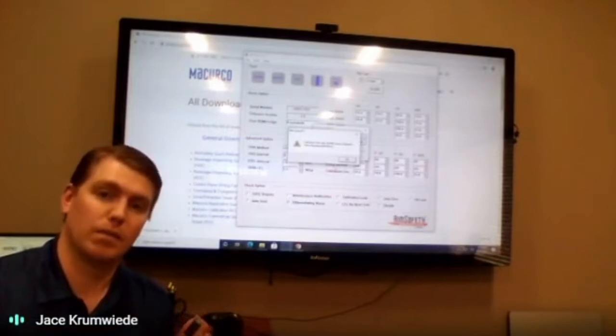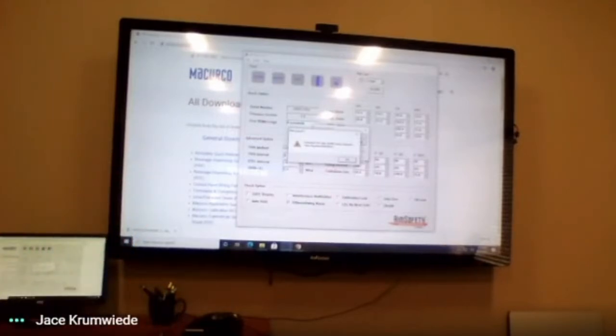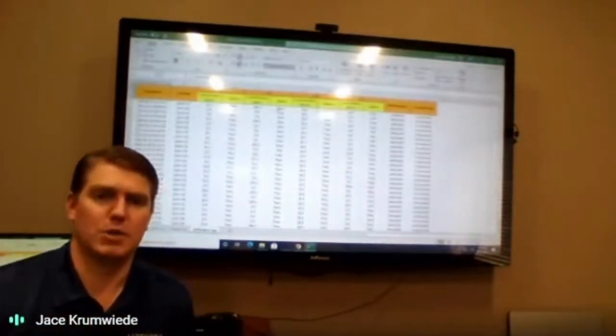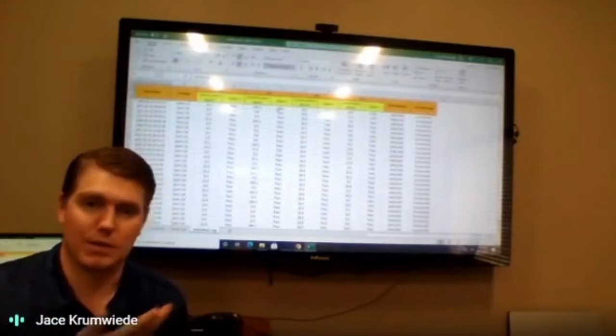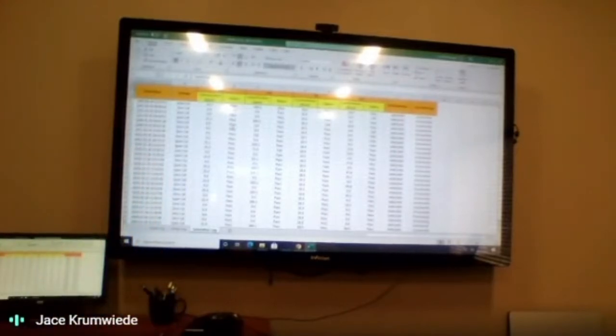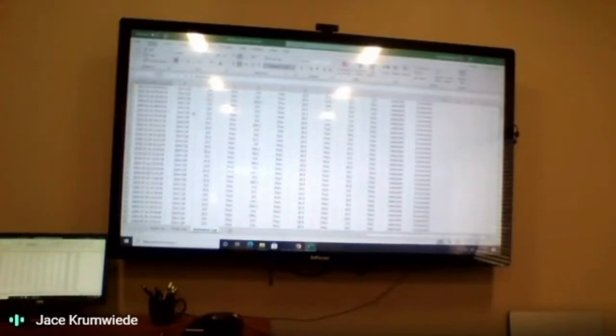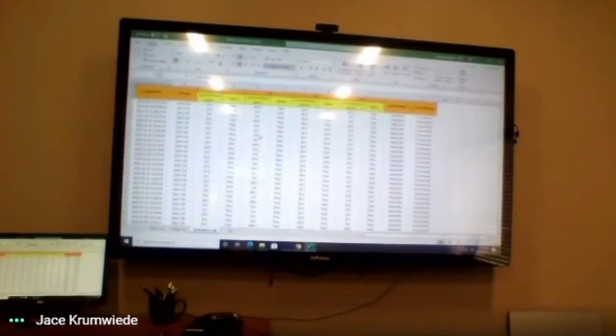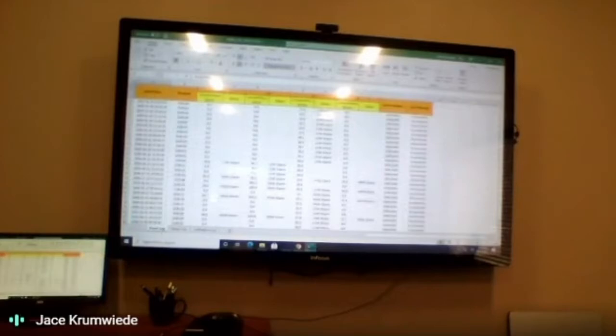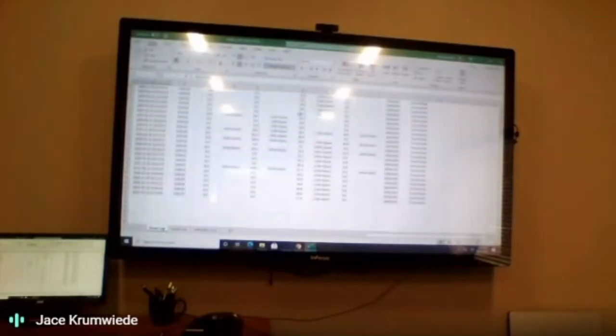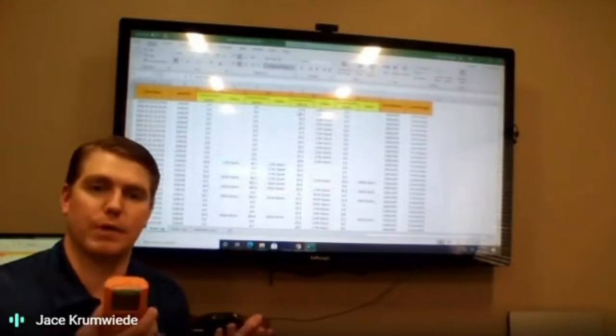Yes, yep, so it will show the name of the unit on the instrument as well. Yep, that is correct. So what I did just there is downloaded the log, and it outputs into a very easy to read CSV file, which you can open within any sort of spreadsheet software such as Excel. And there you'll see the history of logs that it has recorded. I've had this unit for a number of years, so I see some going back all the way to 2018. But this one is showing your calibration log. You'll see a bump log, and then the overall event log that shows any sort of low or high alarms.